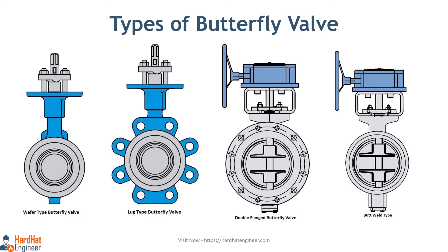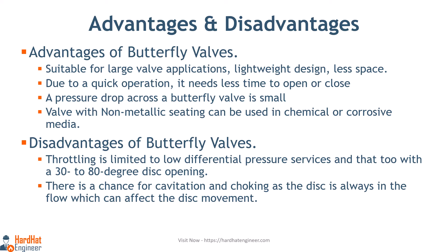There are many design types available such as wafer type, lug style type, flange type, butt-welded ends types, zero offset, double offset, and triple offset. Advantages: butterfly valve is suitable for large valve applications due to its compact, lightweight design that requires considerably less space than other valves. Due to quick operation, it needs less time to open or close. Maintenance costs are usually low, and pressure drop across a butterfly valve is small.